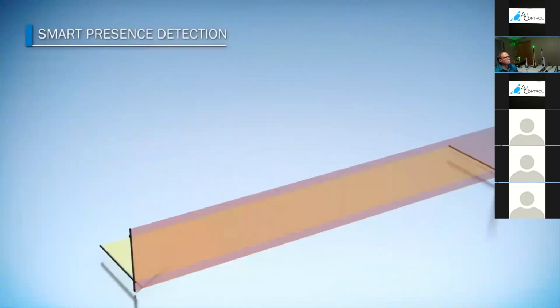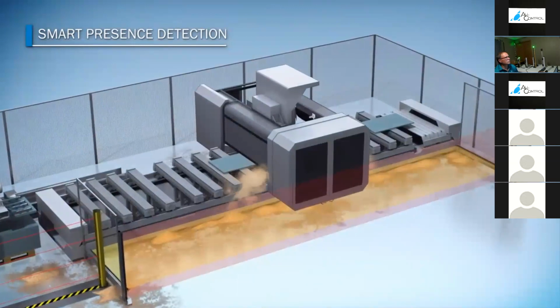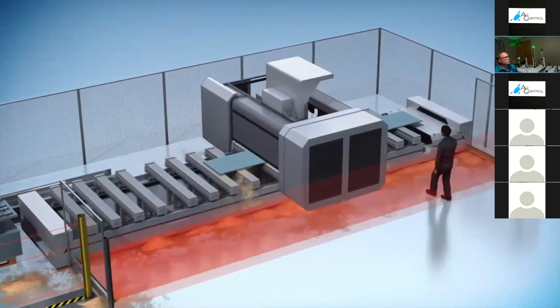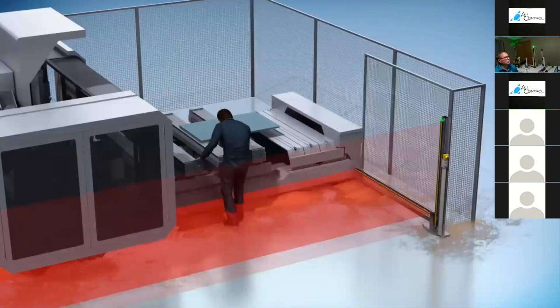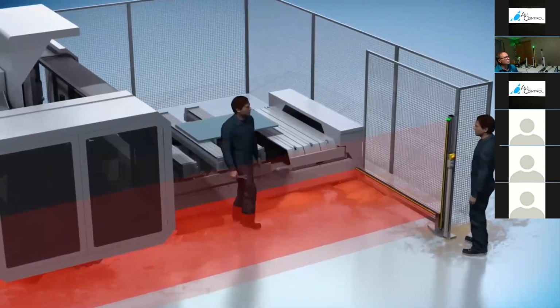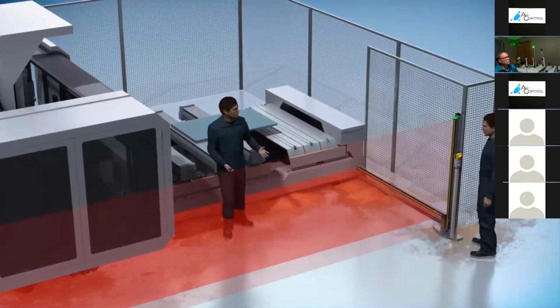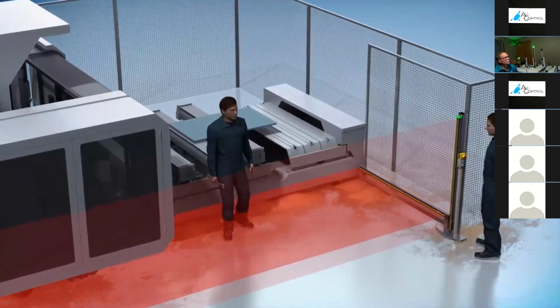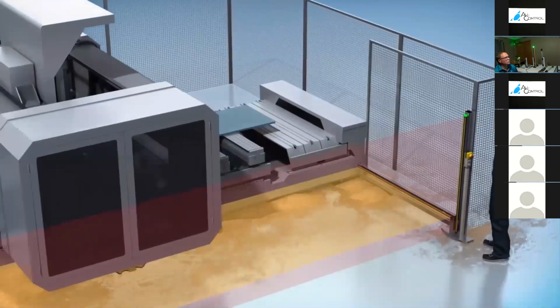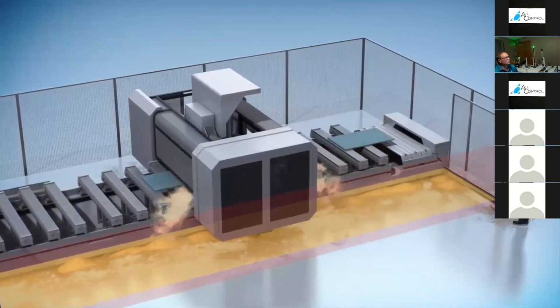The deTec4 uses a host guest cascade, the smart presence detection function. It switches the guest light curtain, which is horizontal here, to sleep mode. In dusty applications, for example in industrial wood processing, the horizontal deTec4 tolerates spinning particles, and the workflow won't be stopped. If the protective field of the vertical deTec4 is blocked, the horizontal system starts protection, and the machine stops. Persons standing inside are now safely detected by the horizontal deTec4. Once all protective fields are clear again, the horizontal system switches to sleep mode, and the machine restarts.